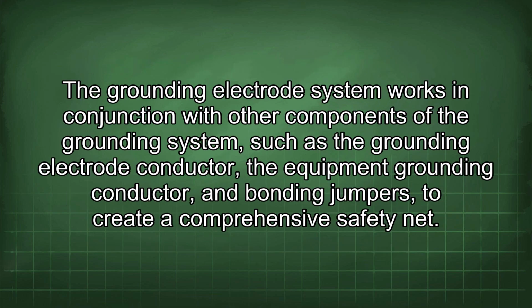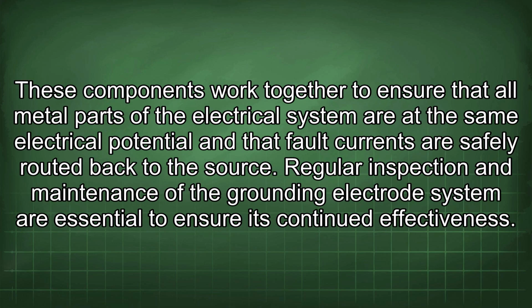The grounding electrode system works in conjunction with other components of the grounding system, such as the grounding electrode conductor, the equipment grounding conductor, and bonding jumpers, to create a comprehensive safety net. These components work together to ensure that all metal parts of the electrical system are at the same electrical potential and that fault currents are safely routed back to the source.